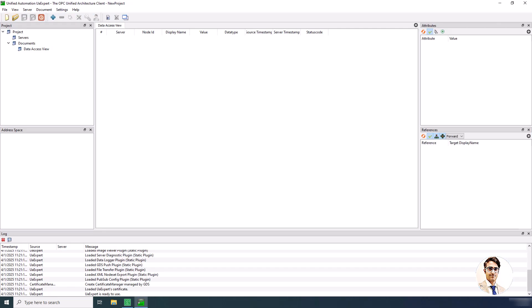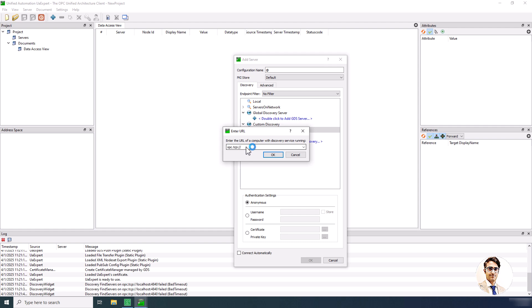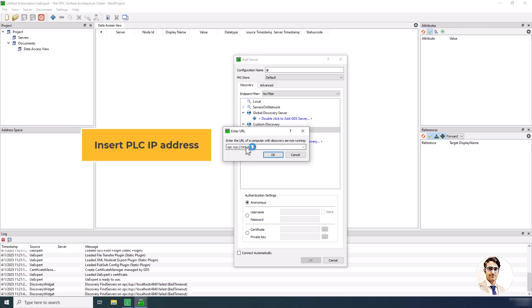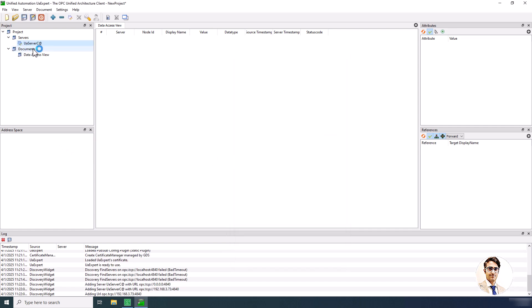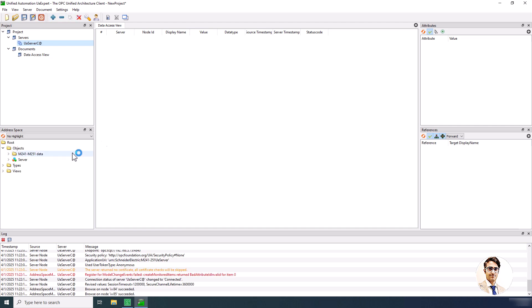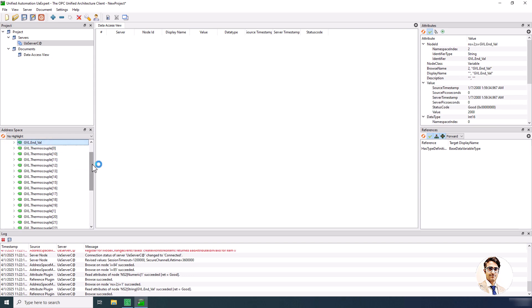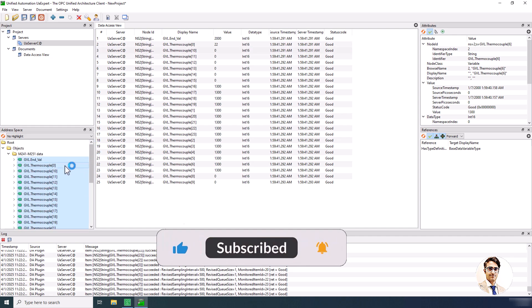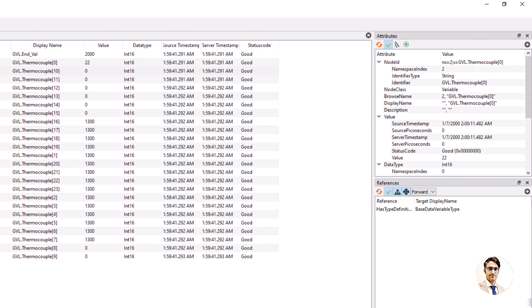To verify OPC UA data transfer, UAExpert software is used. After adding the server and establishing a connection with the PLC, the selected tags appear in the address space window. These tags can then be dragged and dropped into the data access view. The attribute panel provides the node ID for each tag, which is essential for integration with Node-RED. The displayed status confirms a successful OPC UA connection.